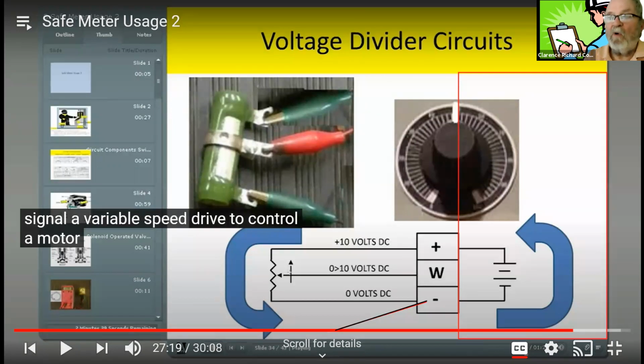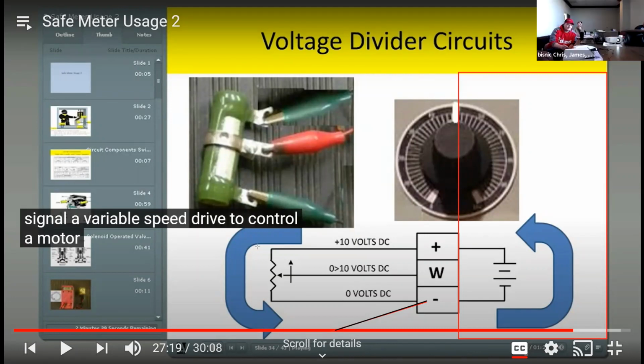Wires are bad. Okay, you haven't determined that yet. You could be checking right here on the pot terminal itself. If I'm on the pot terminal itself and it says 0 volts, what does that tell you? That's getting bad. You had 10 volts here, you had 10 volts here, you had 0 there, you had a broken wire.